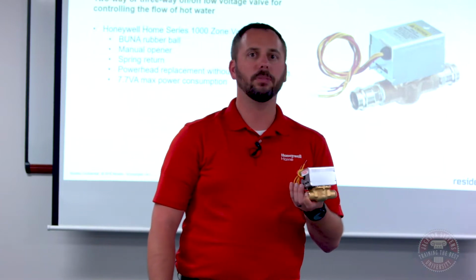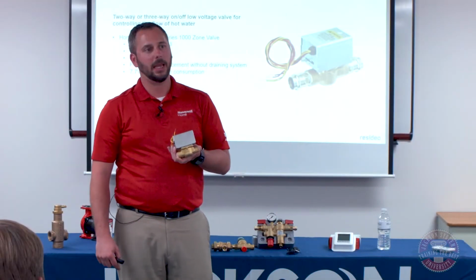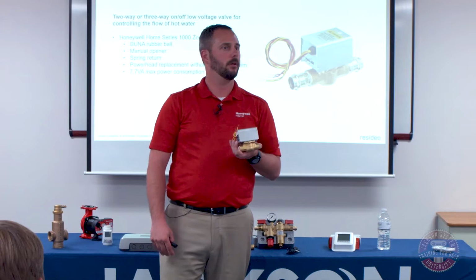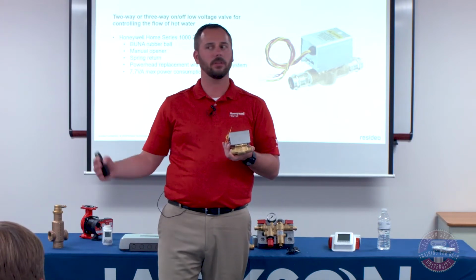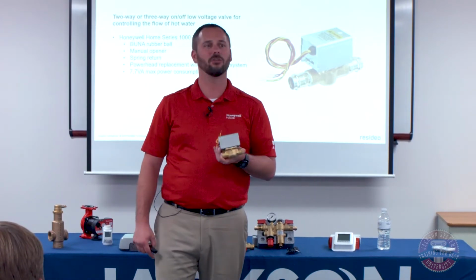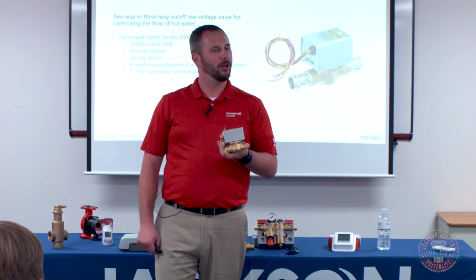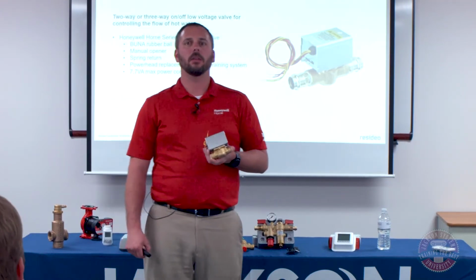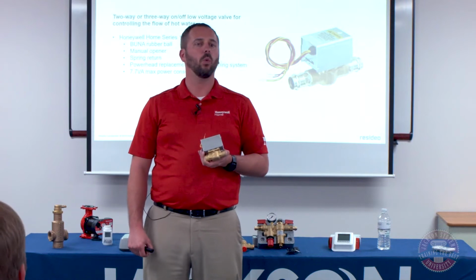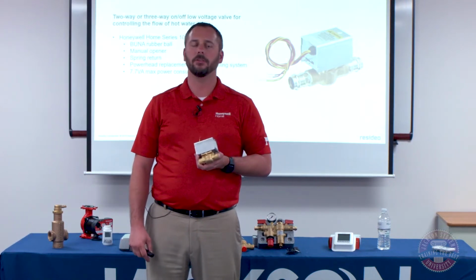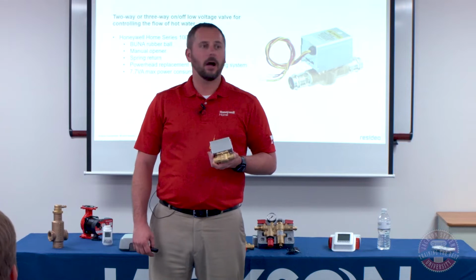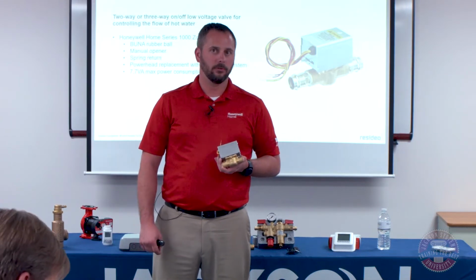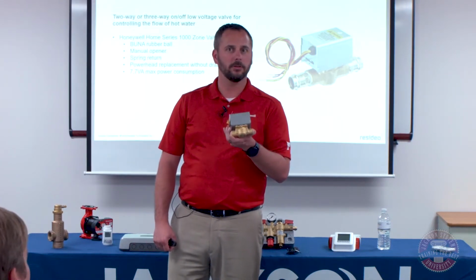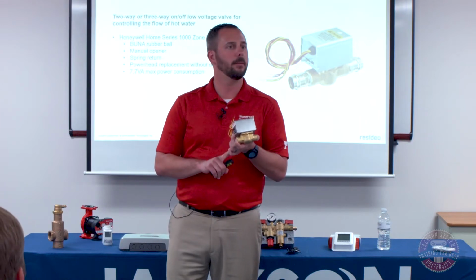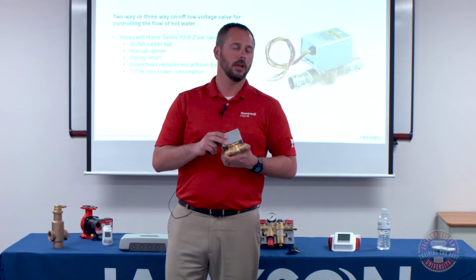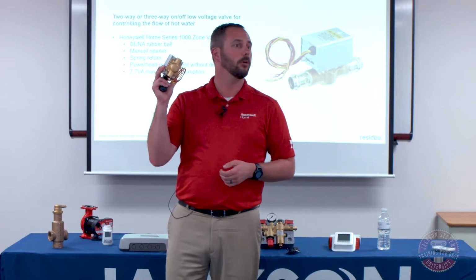Because this is a mechanical piece of equipment, just like a pump. Mechanical pieces of equipment, after so many cycles of operation, everything will eventually fail. I wish to say ours never would, but ours will fail eventually. Depending on the use and the water quality, there are a lot of different factors in how long a valve will last. If you've got a lot of junk in the system, and you don't have any boiler inhibitors or chemicals inside of it, there is a lot more strain on the motor.